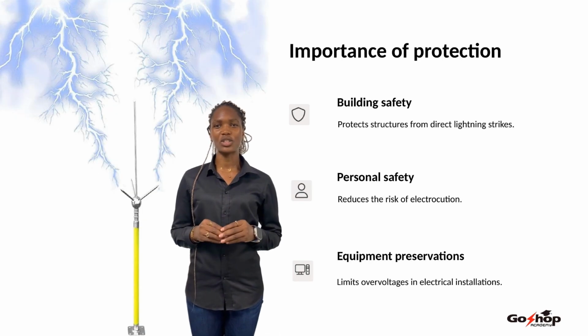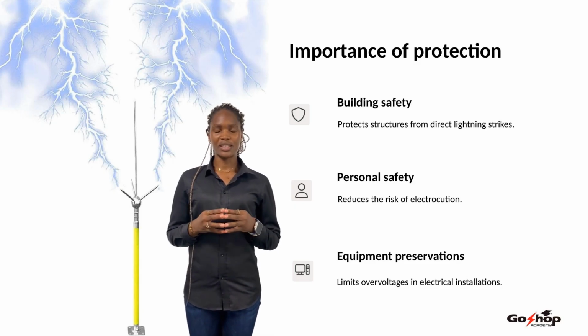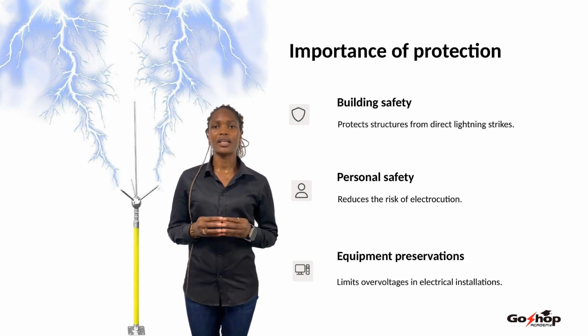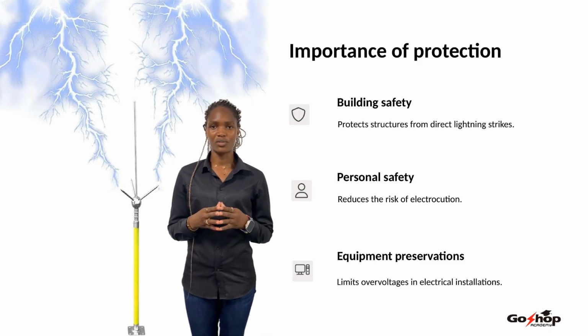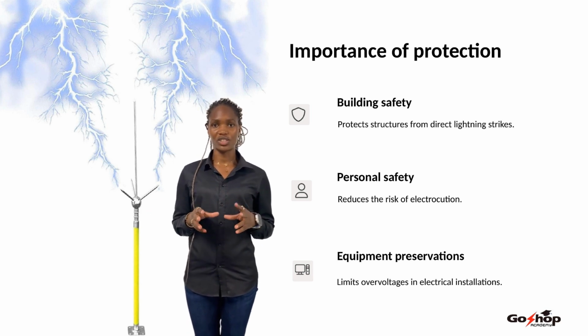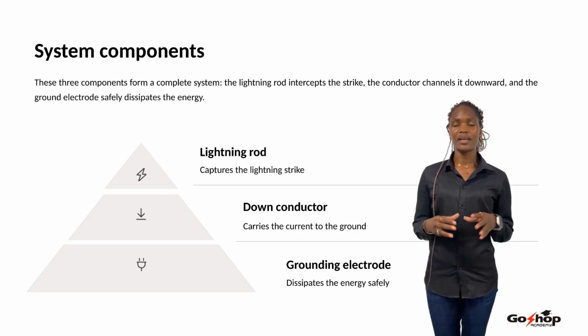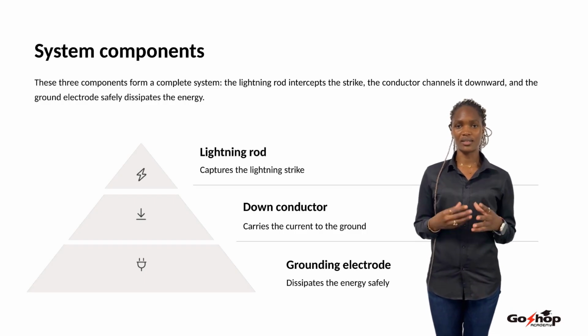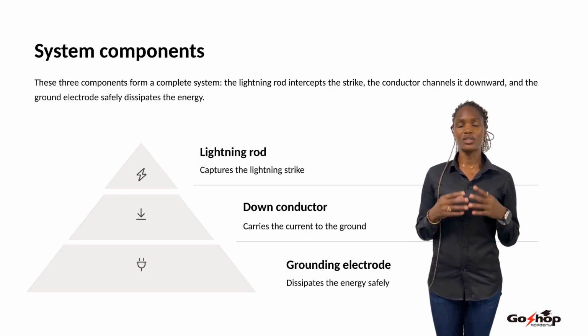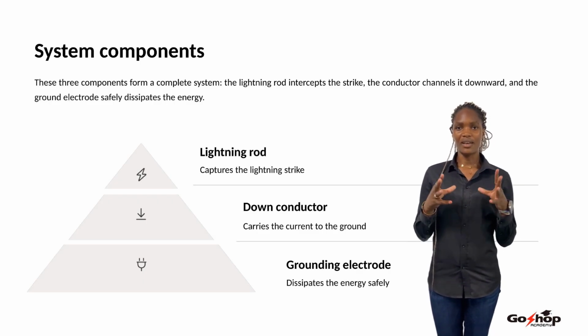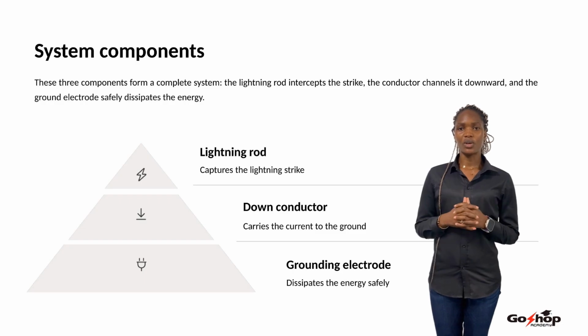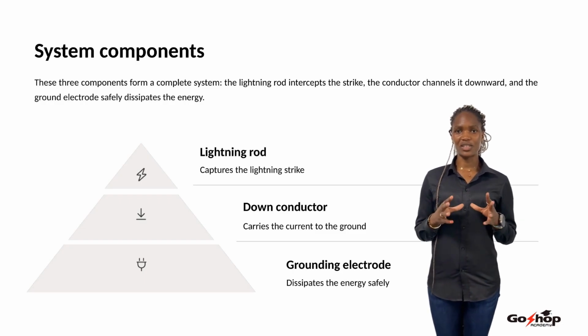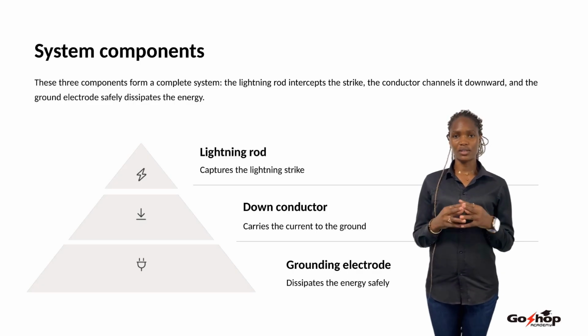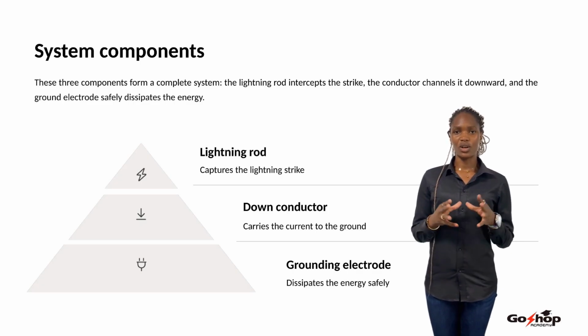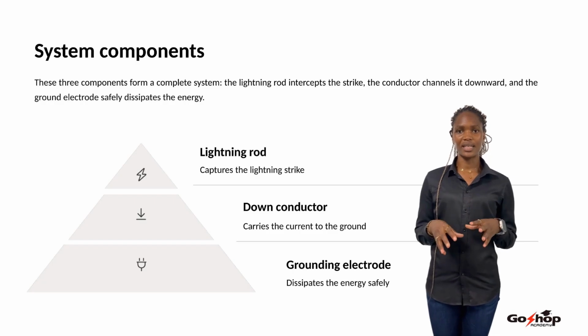Lightning protection is essential for several reasons. It ensures building safety by protecting against direct strikes. It protects people by reducing the risk of electrocution. It also helps preserve equipment by limiting overvoltages in electrical installations. A lightning protection system has three parts: the lightning rod captures the lightning strike, the down conductor carries the electricity to the ground, and the ground connection safely disperses the electricity into the soil. In short, the rod captures the lightning, the conductor guides it down, and the grounding eliminates it.